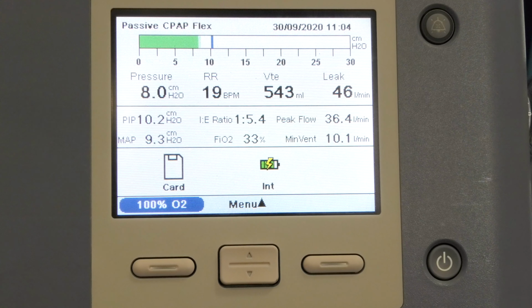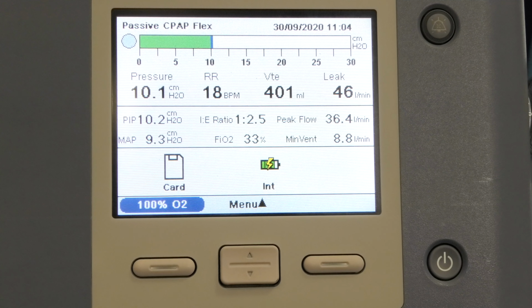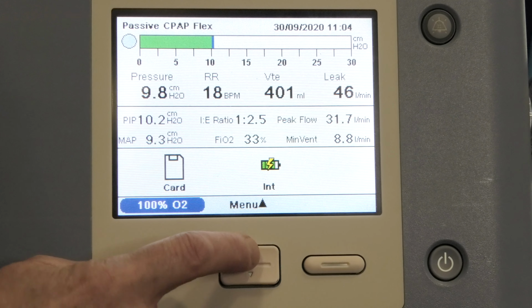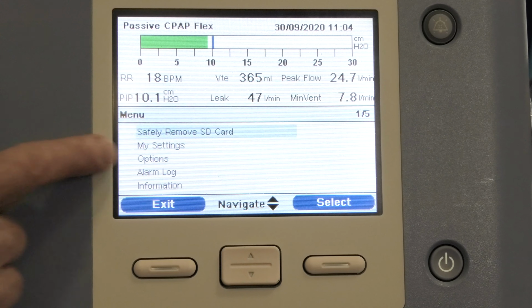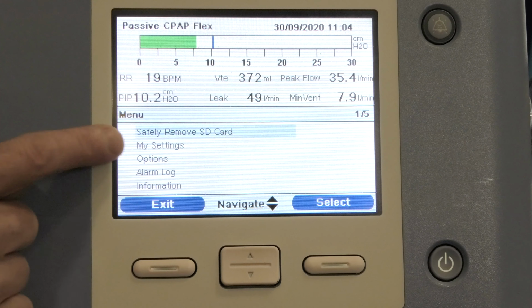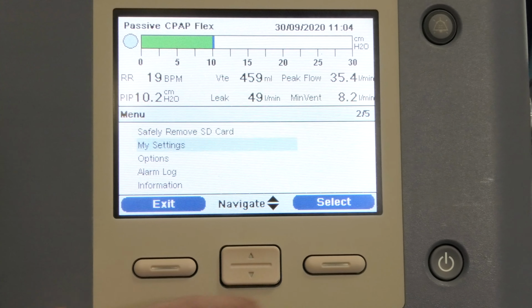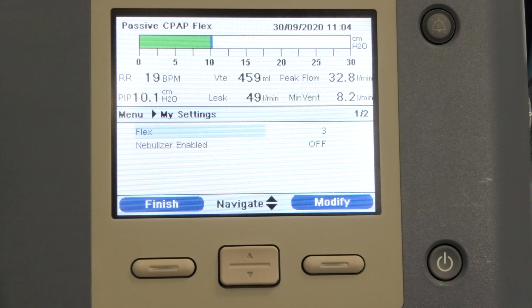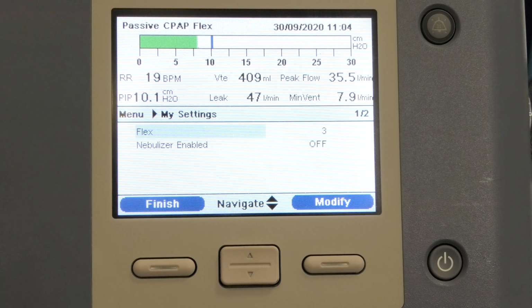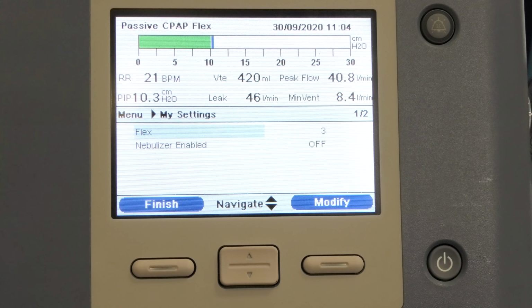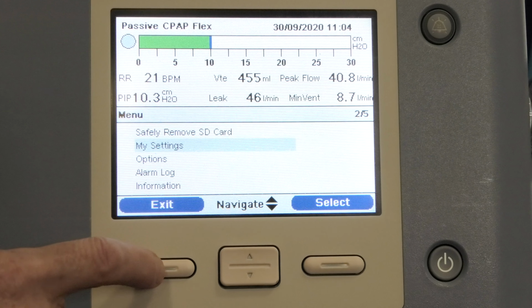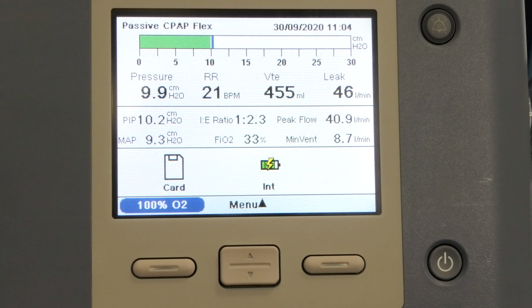Okay. Sometimes the ventilator is left in a locked state. So if we go into our menu, you can see settings and alarms aren't there anymore. It just says my settings. If I go into my settings to change into CPAP or BiPAP or make a change to the settings, it won't allow me to do it. I'm going to come out of there and show you how to unlock the ventilator.